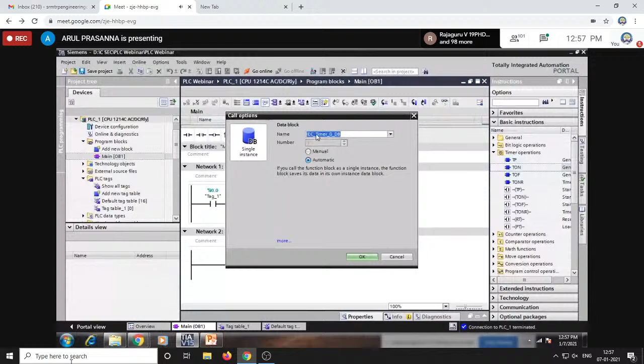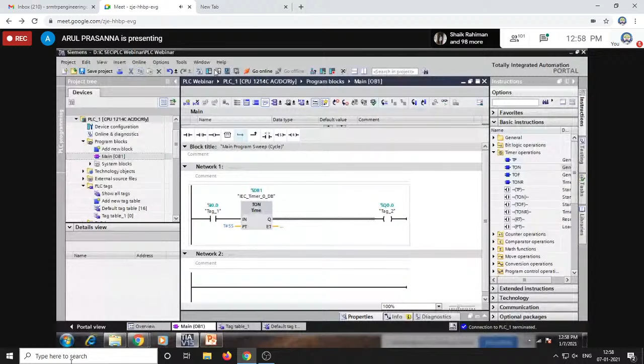I am going to give a delay of 5 seconds. If I type 5 in my preset time, it will take it as 5 milliseconds. The base value available here is in milliseconds, so if you want to enable your timer for 5 seconds, you can give it as 5000. So I am giving it as 5000 now, and I am downloading this. Any change you make in your program has to be downloaded immediately to your PLC, then only it will be reflected. Now it is downloaded.